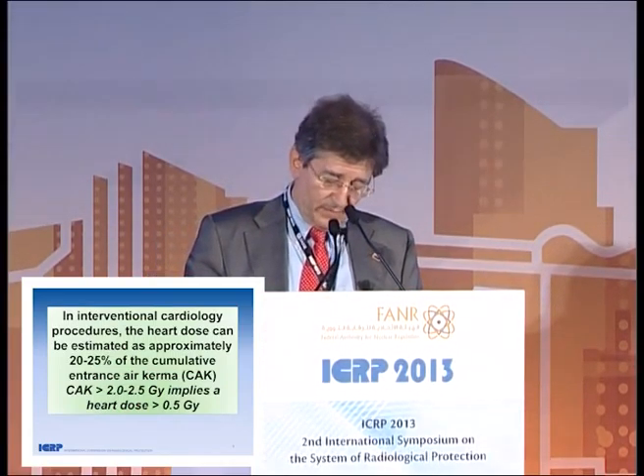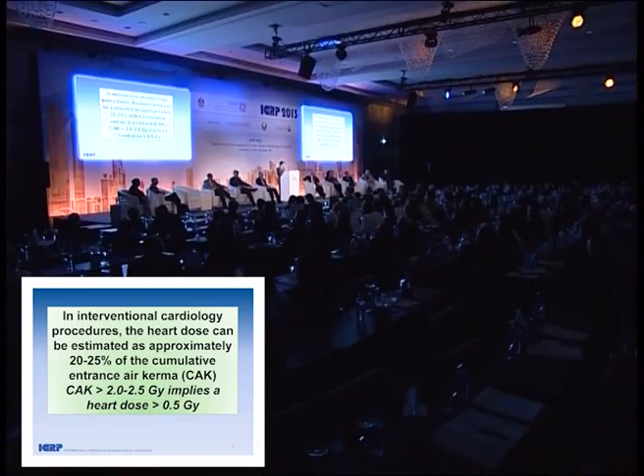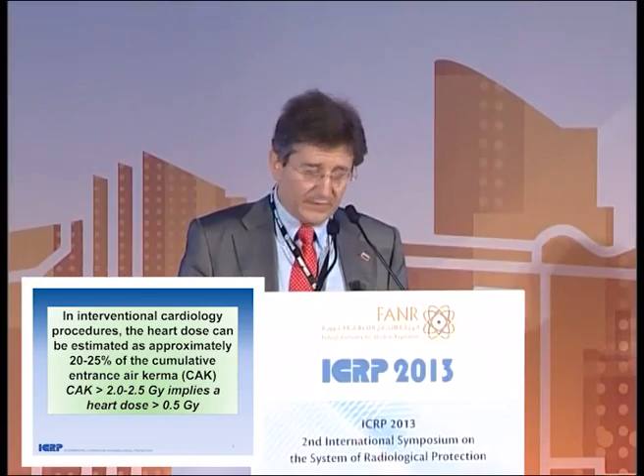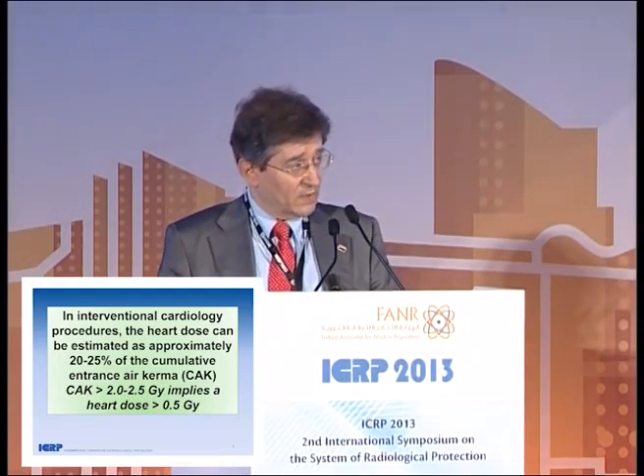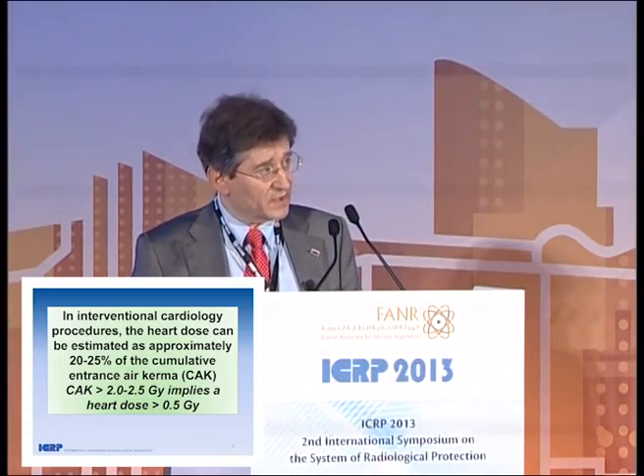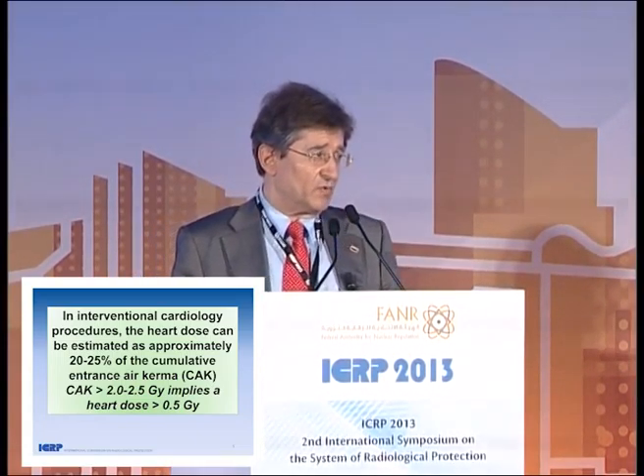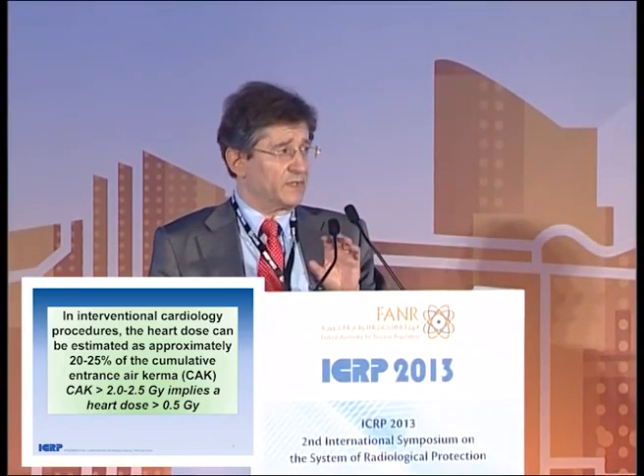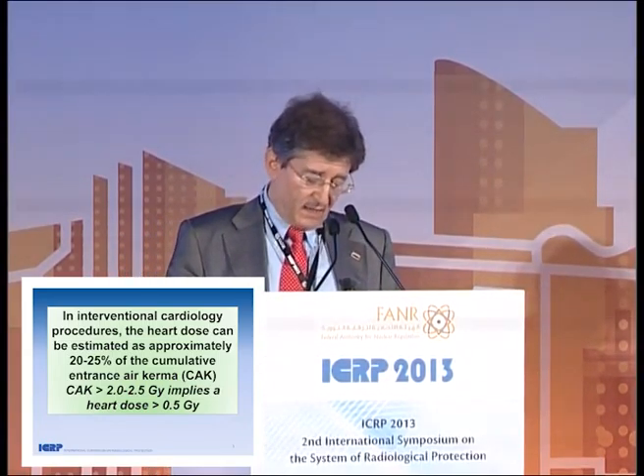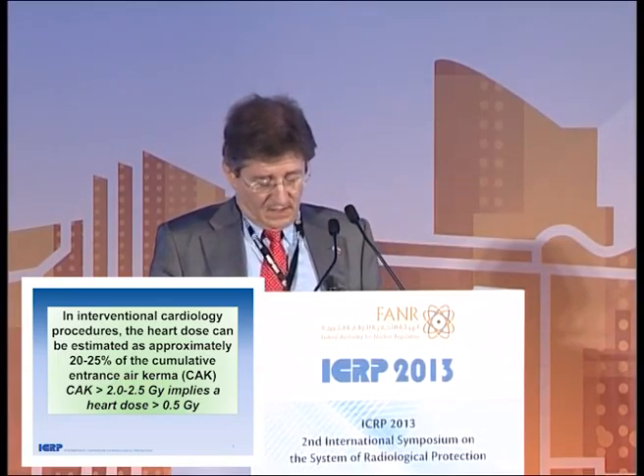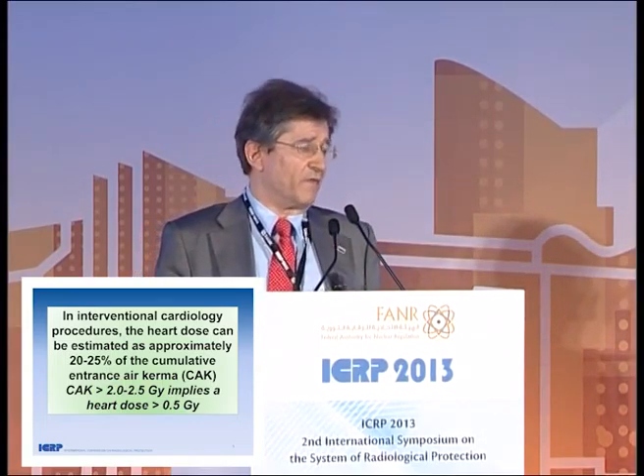Concerning interventional cardiology procedures, the beam moves a lot during the procedure as we try to visualize the coronary arteries, but always there is some dose to the heart. Using Monte Carlo calculations, the dose to the heart is approximately 20 to 25% — it could be 15% if we are using collimation — of the total cumulative entrance air kerma. If the cumulative kerma is higher than 2 or 2.5 grays, this involves a heart dose that could be higher than 0.5 grays.